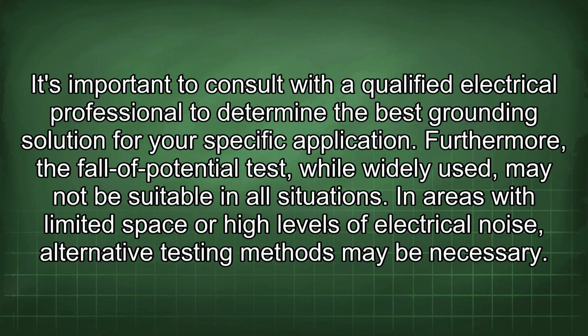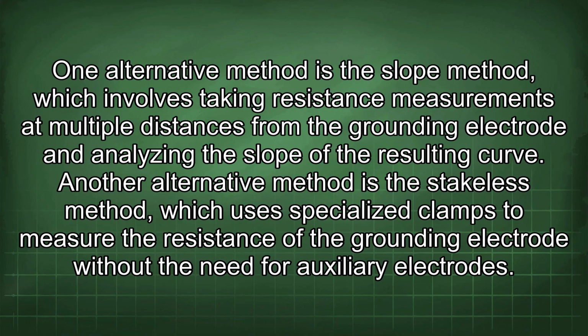your specific application. Furthermore, the fall of potential test, while widely used, may not be suitable in all situations. In areas with limited space or high levels of electrical noise, alternative testing methods may be necessary. One alternative method is the slope method, which involves taking resistance measurements at multiple distances from the grounding electrode and analyzing the slope of the resulting curve.